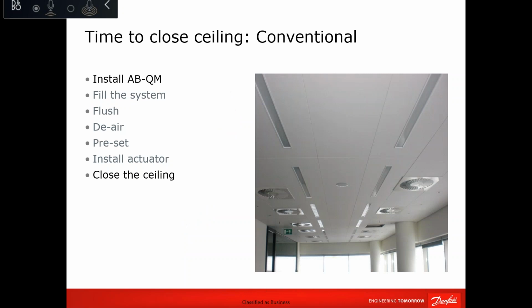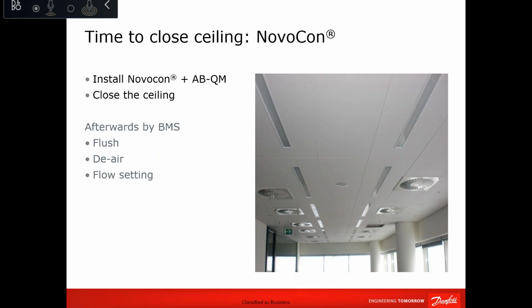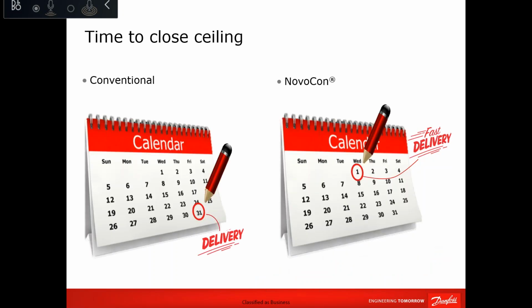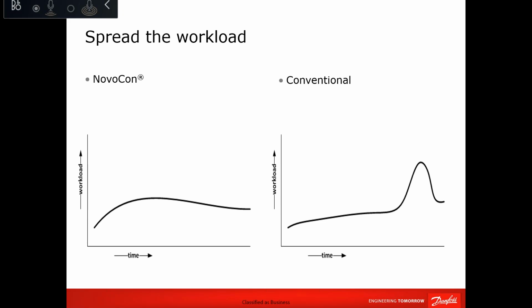So in normal installation, you need to install the valve, fill the system, flush the air, preset, install the actuator, then close the false ceiling. In case of the smart actuator, you will install the valve and actuator, close the false ceiling, and then after, from the BMS, you can do the flushing, the de-air, and the flow setting. So this will save a lot of time and will reduce the spread of the workload. So you will not find the electrician, pipe fitter, duct installation, everything at the same time. At least you have removed one of the tasks, which is the actuator and valve.